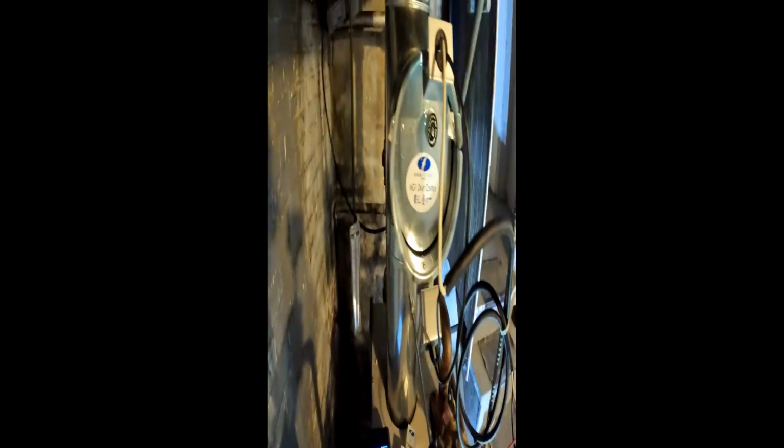So we'll see what happens here. I'm going to turn this on. You can see the damper moving. So let's keep track of the parts per million. If they're going up, we need to have the inducer.